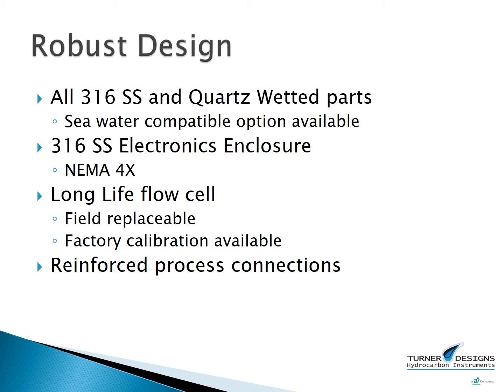For a long lifespan in a challenging field environment, the TD120 is made from all 316 stainless steel and quartz wetted parts with reinforced process connections. The enclosure of the TD120 is also made from 316 stainless steel and has a NEMA 4X design. The components of the instrument are modular for easy field replacement without assistance from the factory, and factory calibration is available for a new flow cell for quick installation.